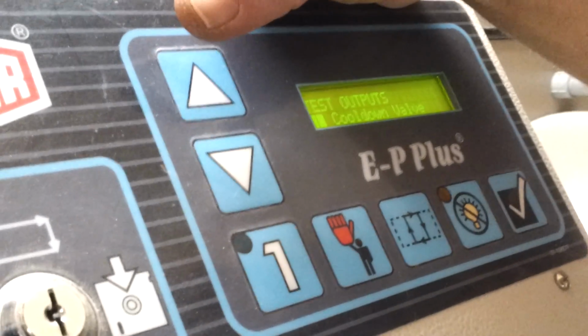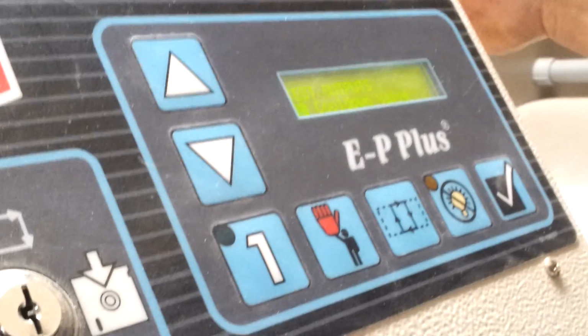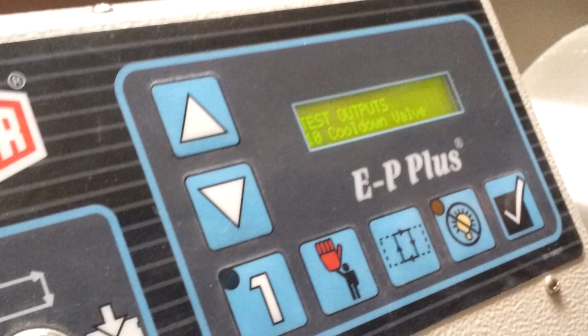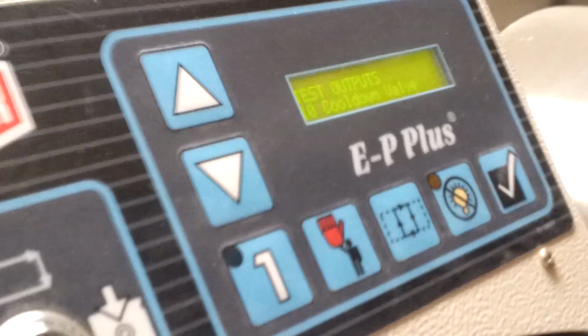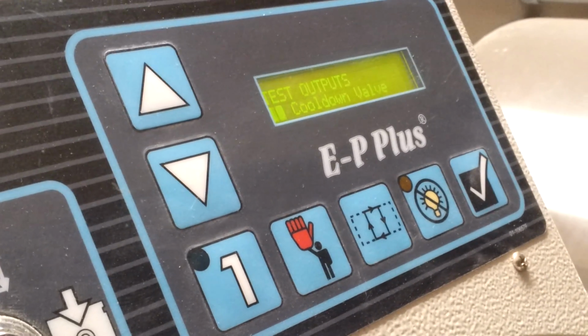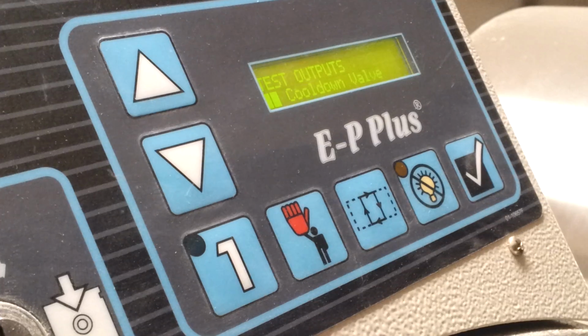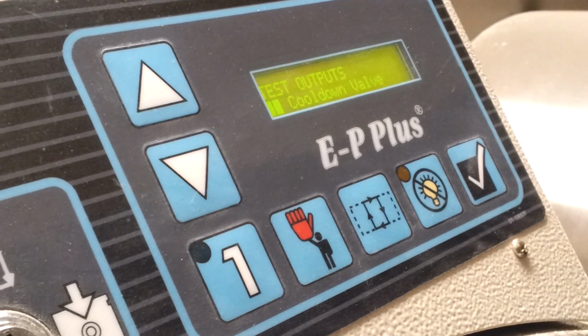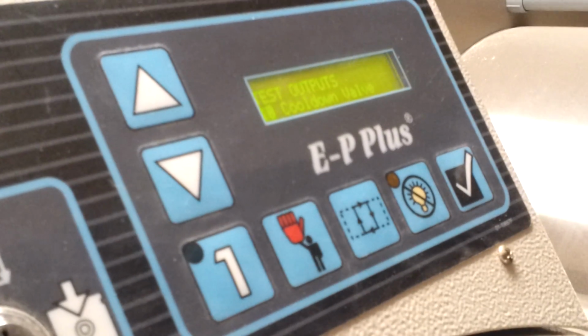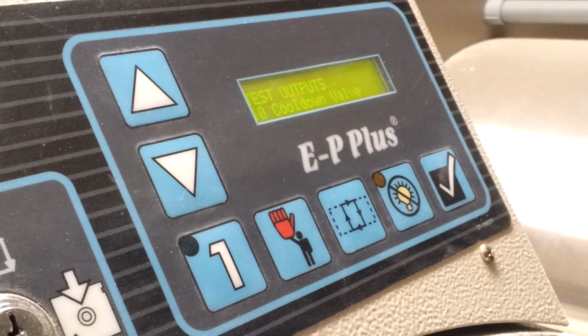So if you have trouble with the machine and you blow a fuse in the back, it's a good way. You can put a new fuse in and go through and test the output until you get to the point of what's causing the fuse to be blown. As soon as you select that particular function of the machine, it will blow the fuse and you'll know right where to go to as far as figuring out what is going to ground. So how many different fuses are back there? There's 4. Okay, so 4 different fuses.